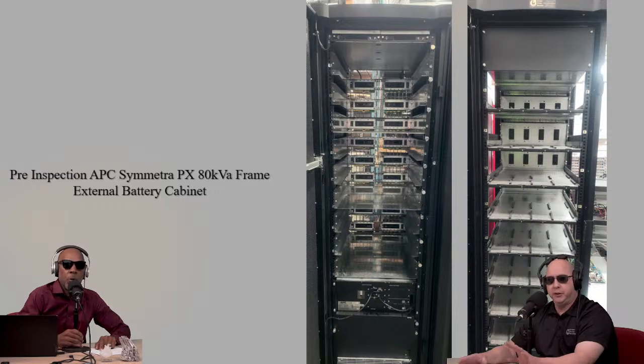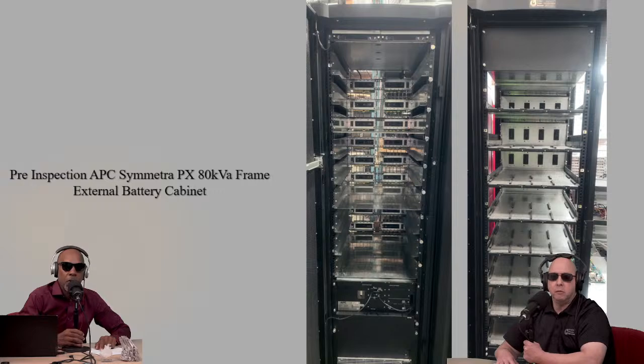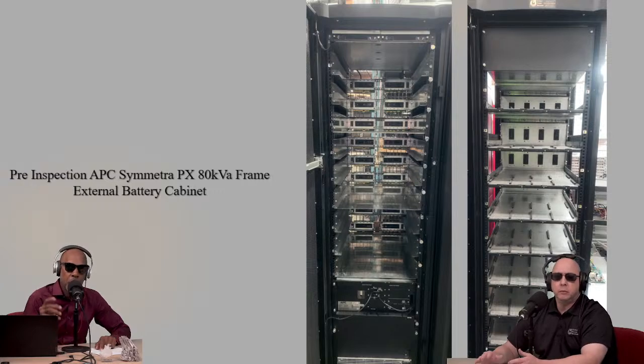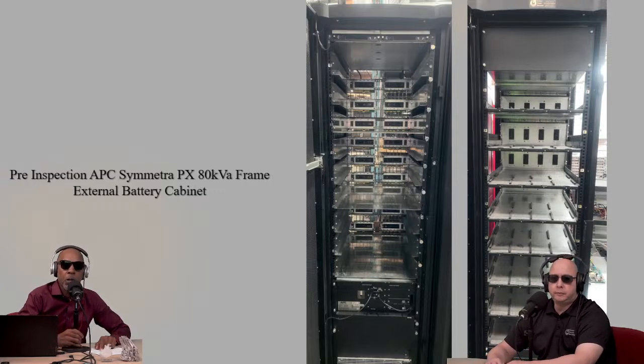That's the 5 things we kind of look for in the beginning, and then as we power it up, if there are problems, we go back to the troubleshooting portion. One of the first things, before it even gets to the technician, that can be pretty obvious is the casters. If this particular UPS simply doesn't roll, you already know you've got a problem, because now you've got to go get a forklift, pick it up, and bring it into the depot.